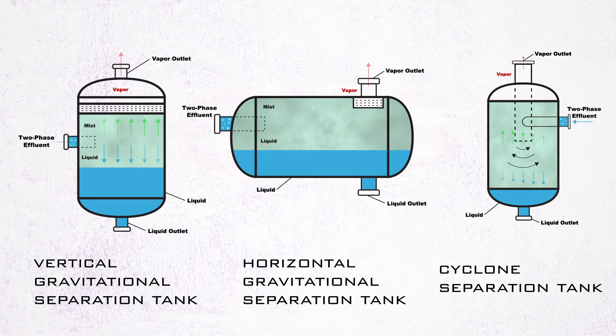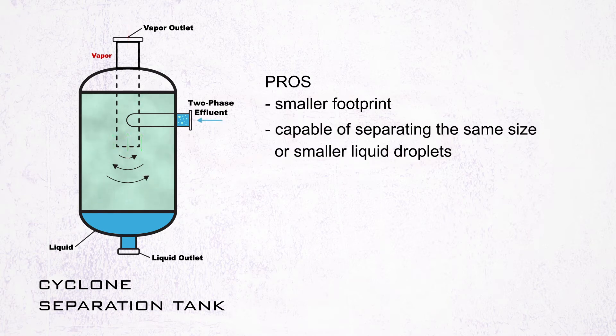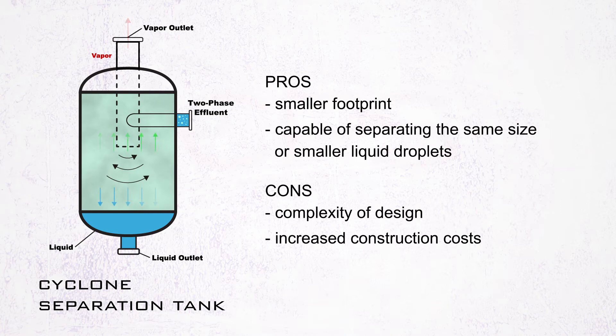Each of these types has its advantages and disadvantages. For example, a cyclone separation tank can be designed with more effective separation than the gravitational types, meaning the tank will have a smaller footprint while being capable of separating the same size or smaller liquid droplets. The trade-off is in the complexity of the design, which carries increased construction costs.